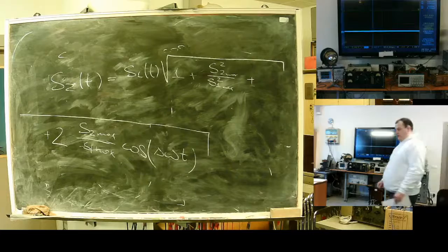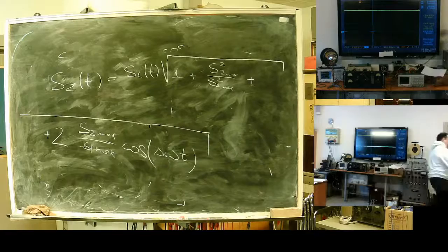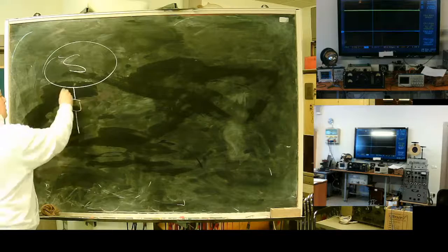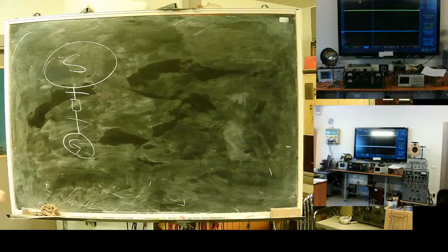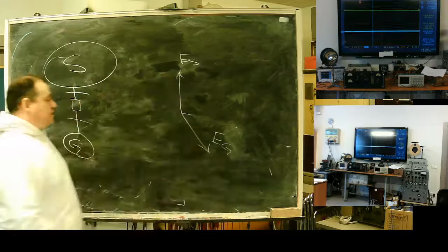Why are we interested in this? First, it's funny. The second one: when we have, let's say, a large power system, a connection point and an AC generator, we need to synchronize the generator with the system with minimal disturbance. Let's say we switch in such a position without synchronizing. What does it mean?